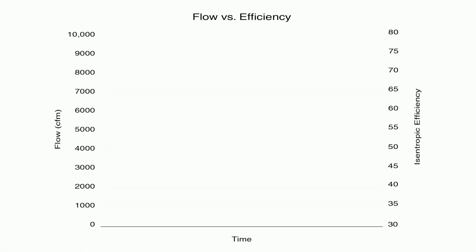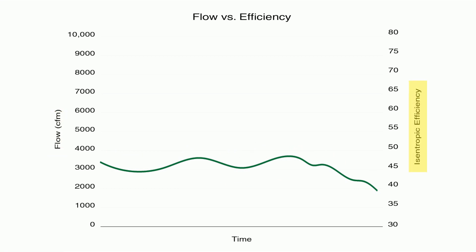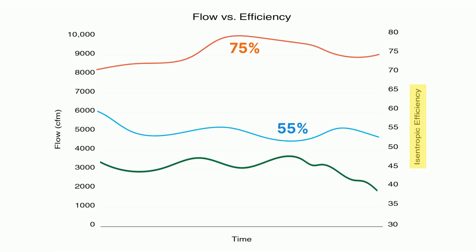To demonstrate, let's have a look at variations in airflow for a typical plant. Most plants see a daily fluctuation in airflow requirements, which are also impacted by the seasons. The flows are typically driven by dissolved oxygen concentrations. As the blowers regulate the flow capacities to meet these demands, the efficiency also varies. Older technologies experience more dramatic fluctuations with efficiency, with their worst coming at lower demands.